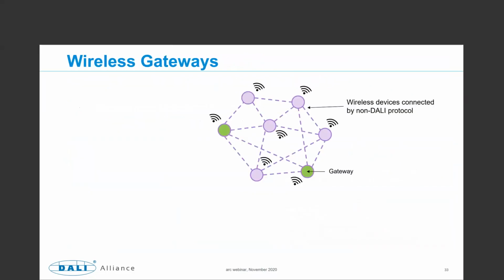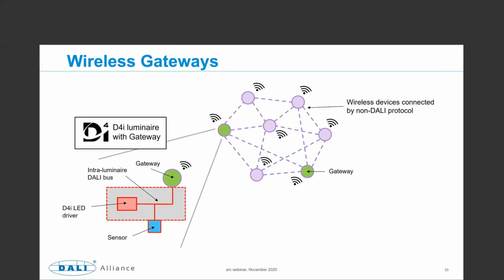Let's look at that in more detail—what's a wireless gateway, and how does it differ from DALI over wireless? Looking at wireless gateways first: here you have a network where the purple dots are wireless devices connected via a non-DALI protocol—they're not DALI devices, just wireless devices. The green dots are gateways to lighting, to DALI. This might be, for example, a gateway to a D4i luminaire, with the gateway mounted on or integrated into the luminaire.